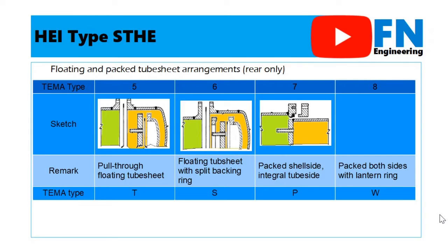This type is using packing in the shell side, meanwhile in the tube side integral with tubesheet. The last type is type 8 or type W. In this type, the tubesheet uses packing in both shell side and tube side and using lantern ring.